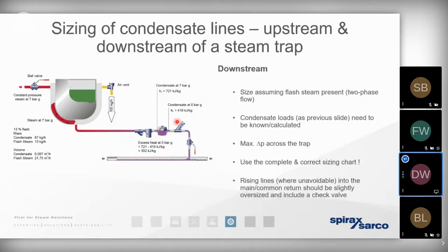So how can the condensate do that? Well, simply put, the sensible heat moves across the steam tables to become total heat. In other words, a certain mass or a certain percentage of that condensate changes state back to flash steam again. But the problem that brings us is that we've got that huge expansion to contend with. So downstream of the trap, we need to size the pipework to allow for that expansion.